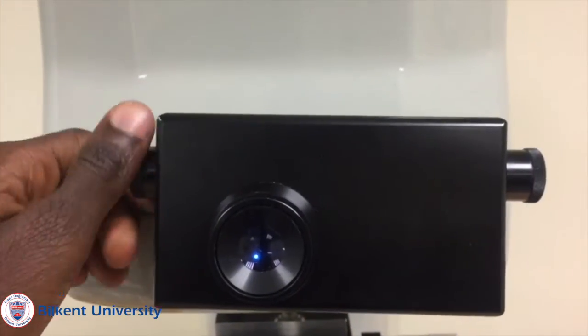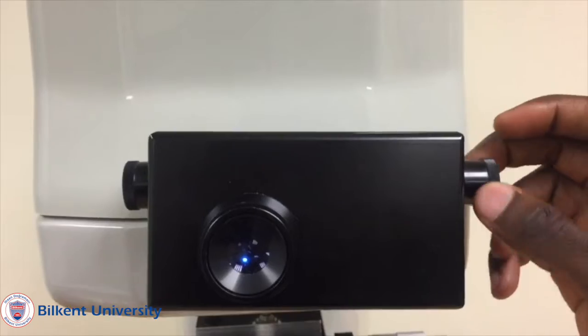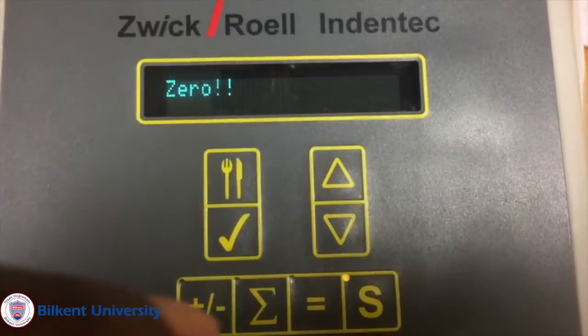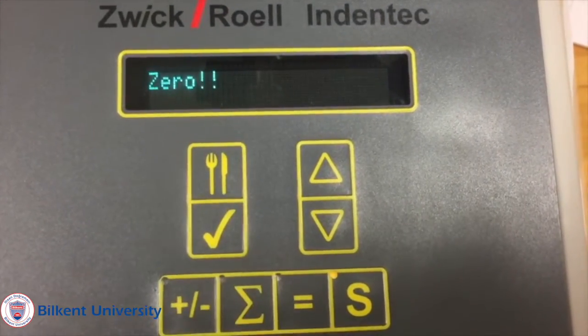Turning the left knob moves both parallel lines at the same time, whereas turning the right knob moves the right line relative to the left line. A calibrated system would show that both lines have been merged together to become one line, and when this is done, we could hit the right tick button on the control screen.